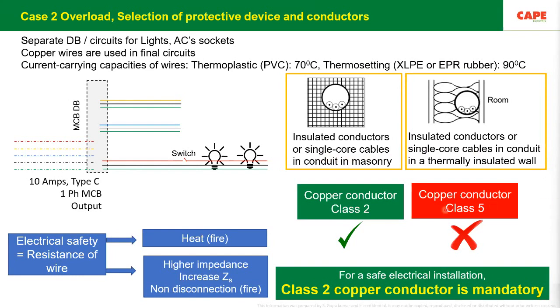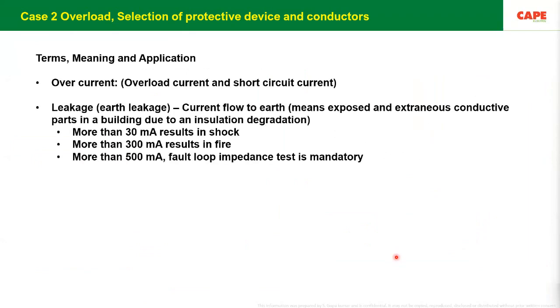Especially here, the issue is one, the sizing of the conductor. Then the second is copper wires pulled through conduits. Class 5 copper is used, which has a higher resistance. The third point is too many wires inside a conduit. If the conduit is, let us say, 1-inch, probably you can pull 5 sets of wires, but instead of 5, probably 10 sets of wires are there. The number of wires is very high, and in most electrical installations the shock protective measures are absolutely missing. I have a case study which I will explain to you later.